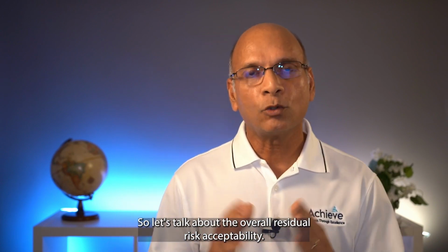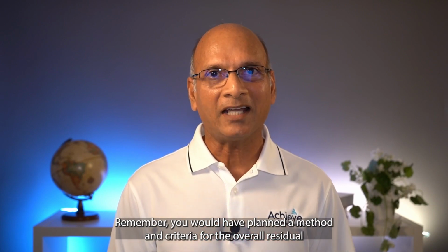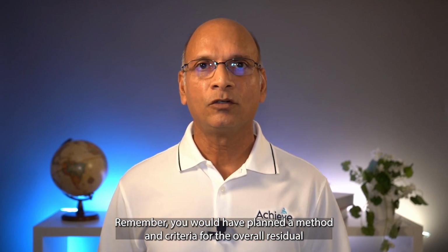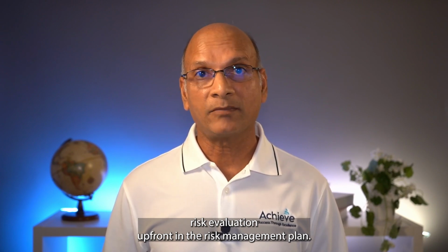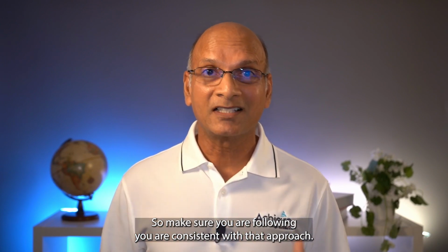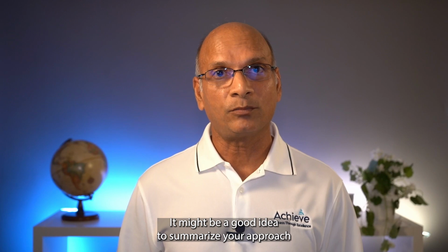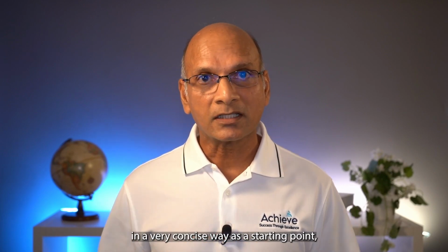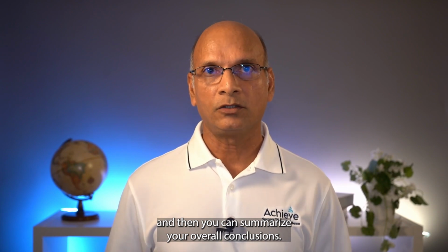So let's talk about the overall residual risk acceptability. Remember, you would have planned a method and criteria for the overall residual risk evaluation upfront in the risk management plan. So make sure you are consistent with that approach. It might be a good idea to summarize your approach in a very concise way as a starting point, and then you can summarize your overall conclusions.